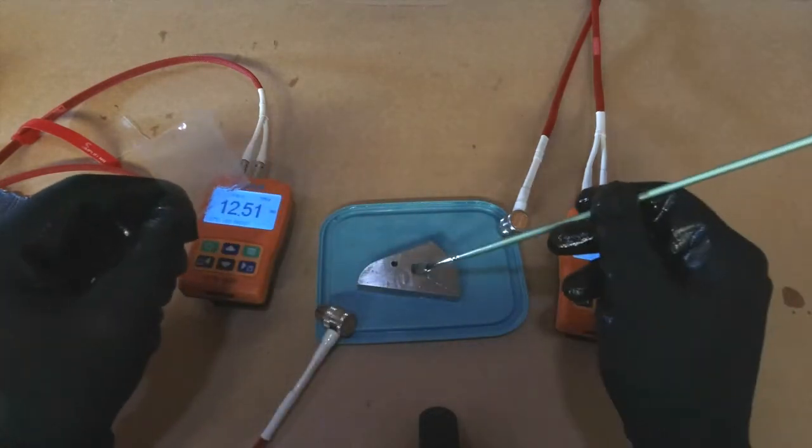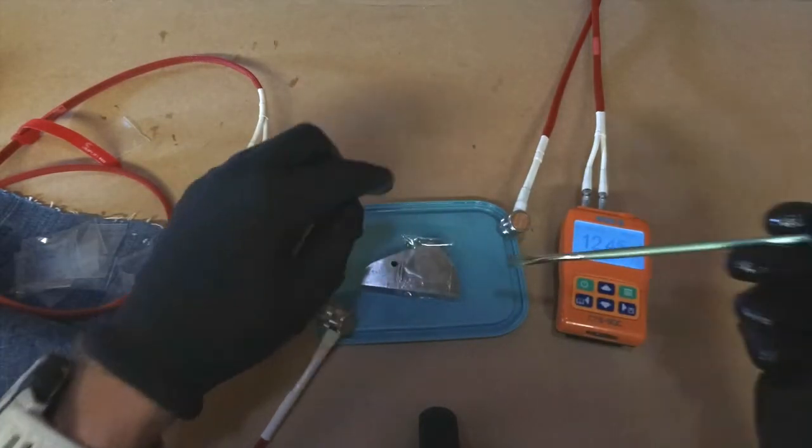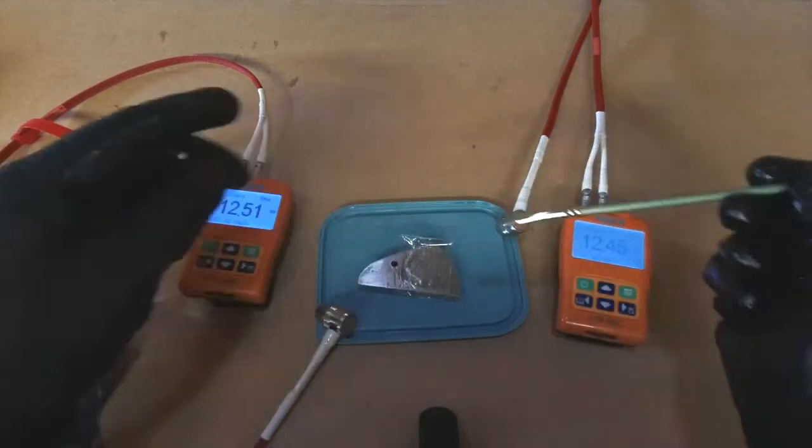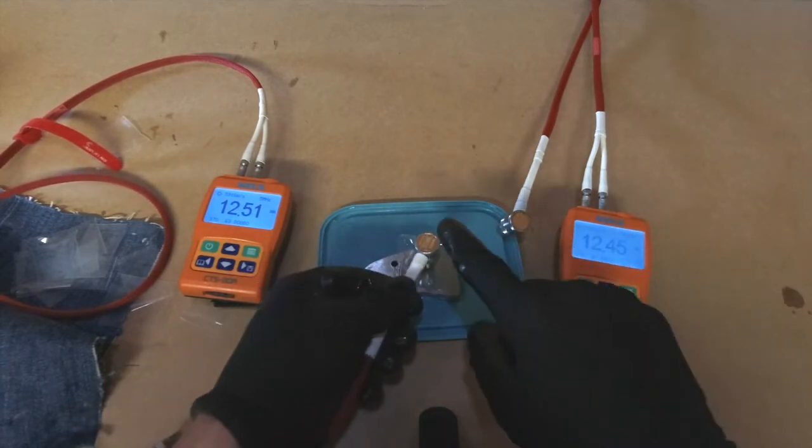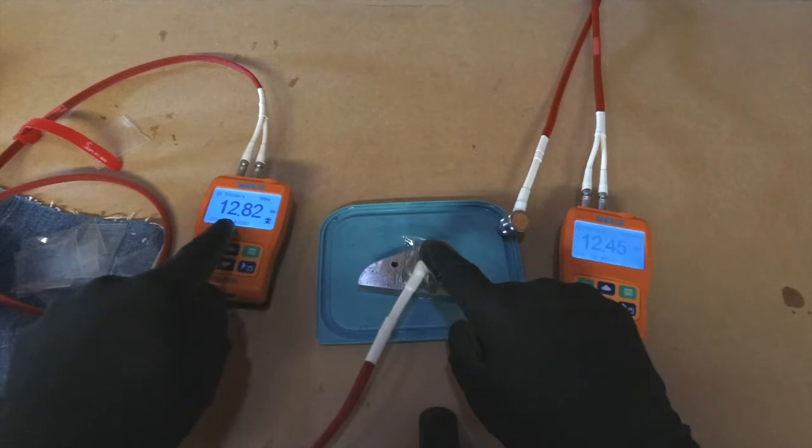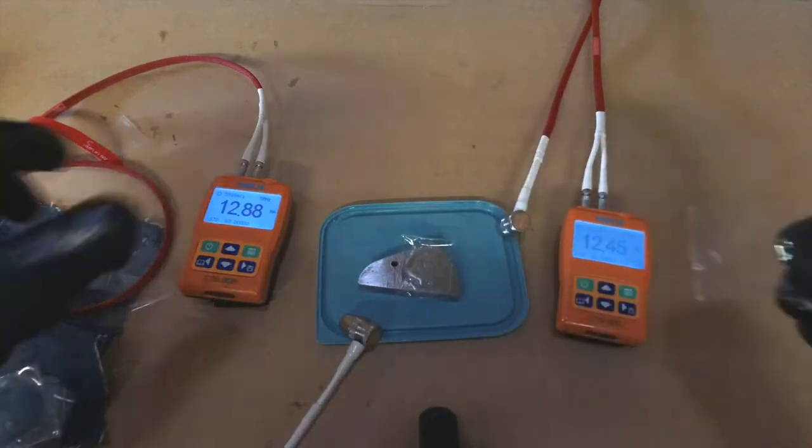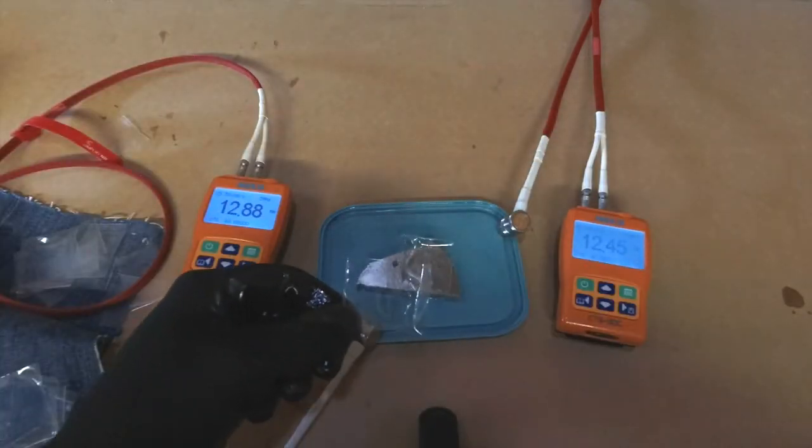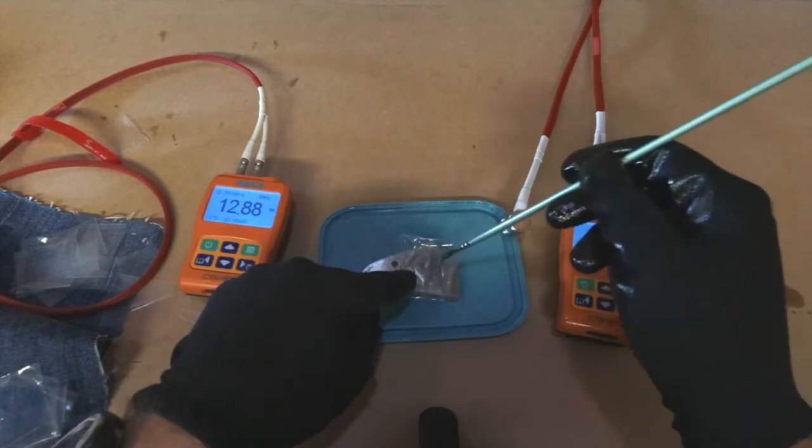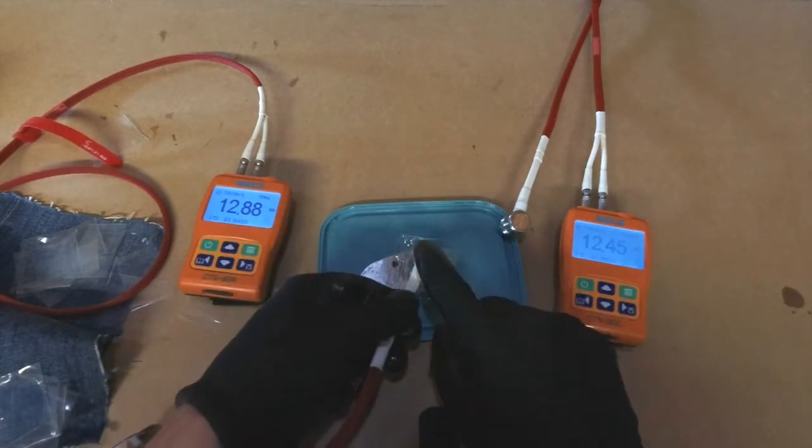What we're going to do is apply this coating now. A small couplant to the top, make sure there's no air bubbles. And what we're going to see, if we can see, is, okay, we're changing thickness. Okay, so we've done one coating. That's now the second one.